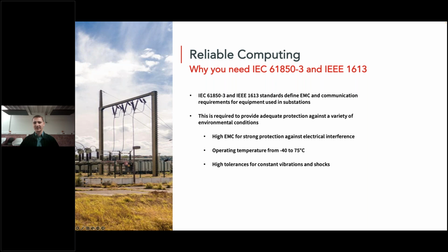That's why hardware really has to be built for use in substations, with high EMC levels from electrical interference and so on. They need to withstand harsh operating temperatures, because they especially need to work perfectly in very cold or very hot temperature situations. From the specification, they need to operate maintenance-free from -40 to +75 degrees.